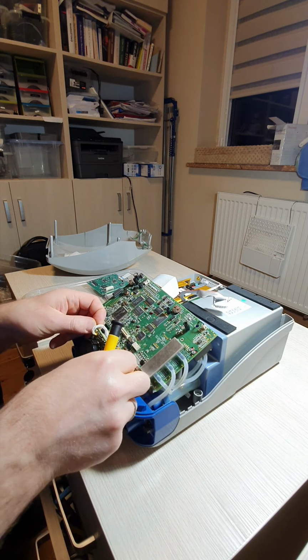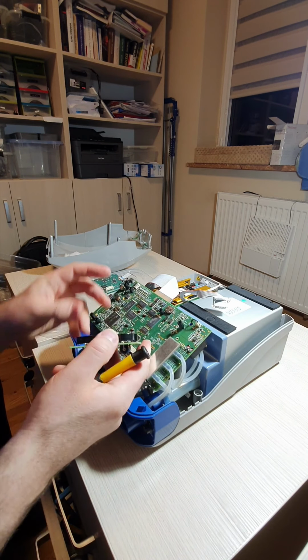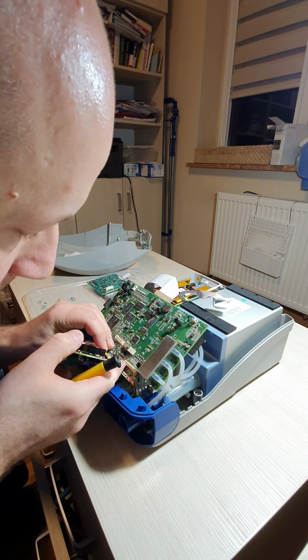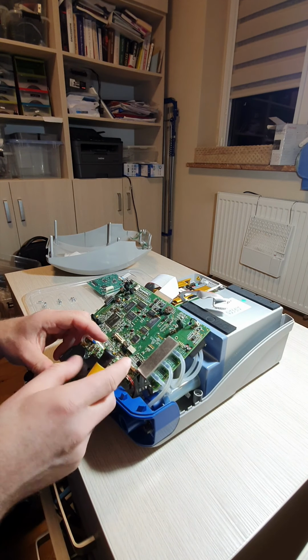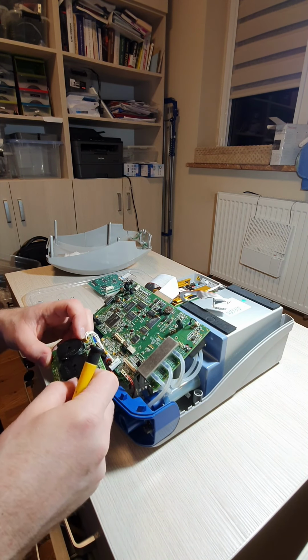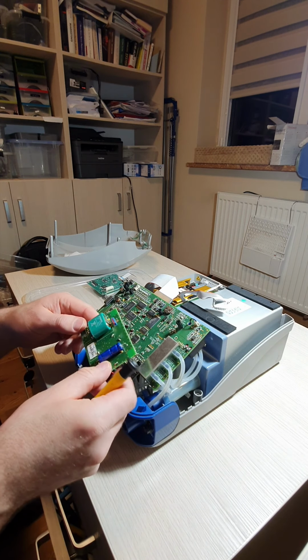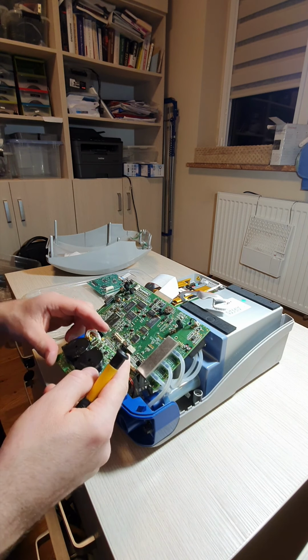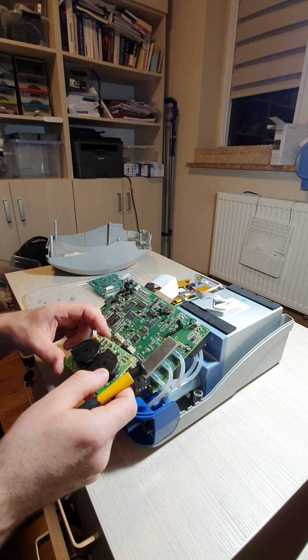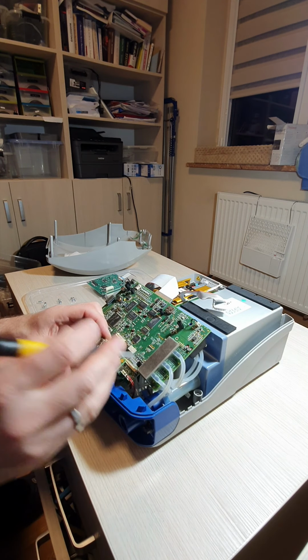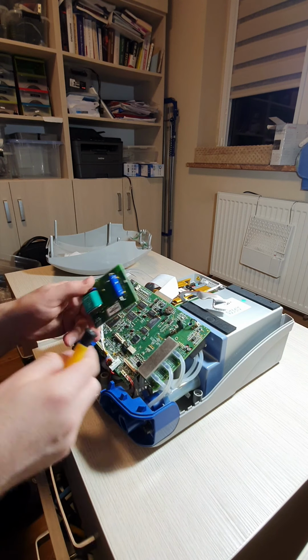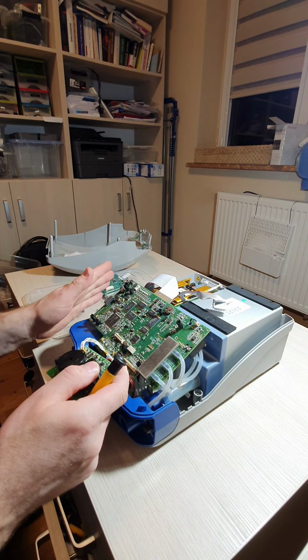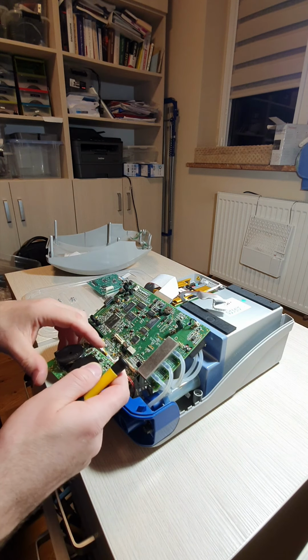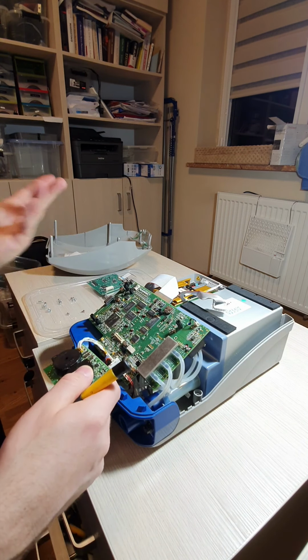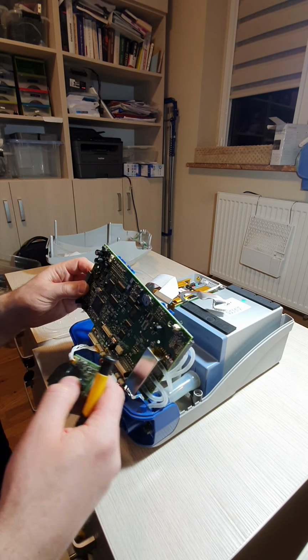This is the buzzer board, which is quite interesting because it's very complex. If you compare the function it does, it simply beeps, but it has a redundant beeper. It has a lot of diagnostic circuits. It has an independent battery with a charger, and it has a full bridge driver on it, and battery charger, DC-DC converter, a lot of stuff to make sure that even when everything breaks, there is no power supply, the battery is depleted, this still will beep, and will simply set the alarm when something's wrong.